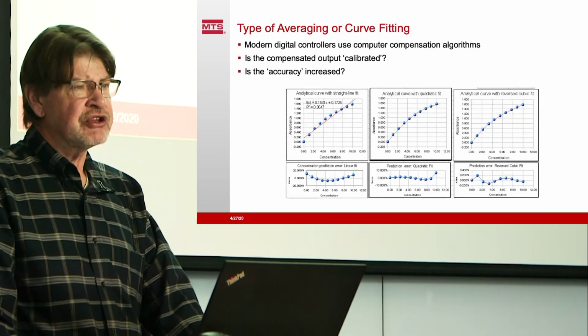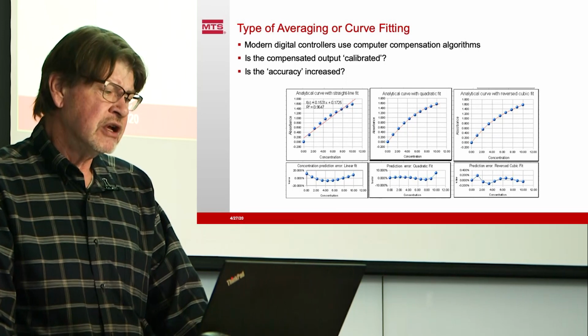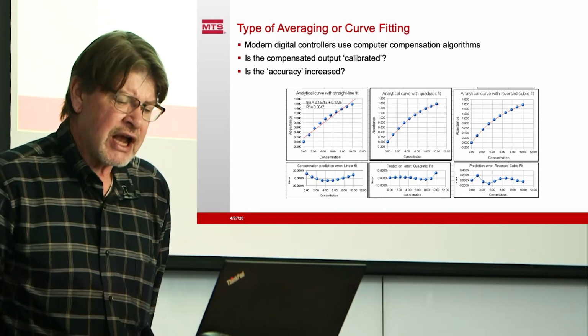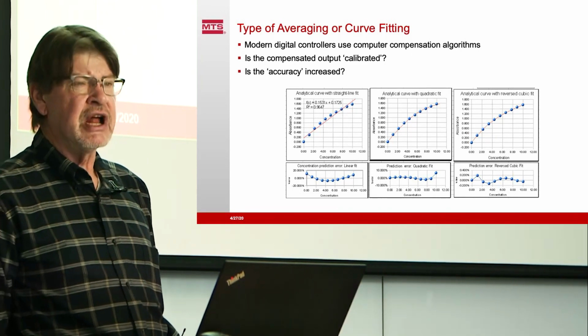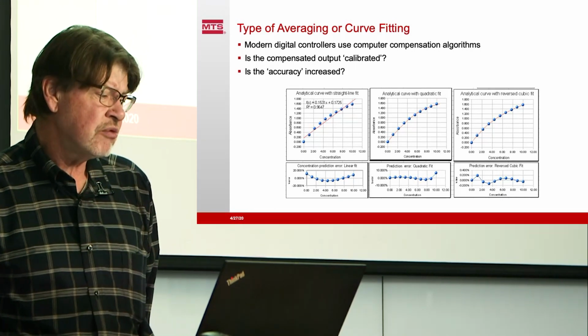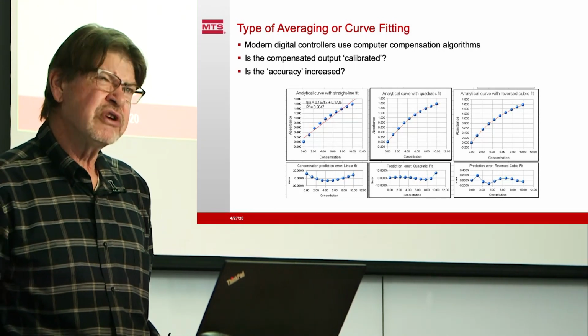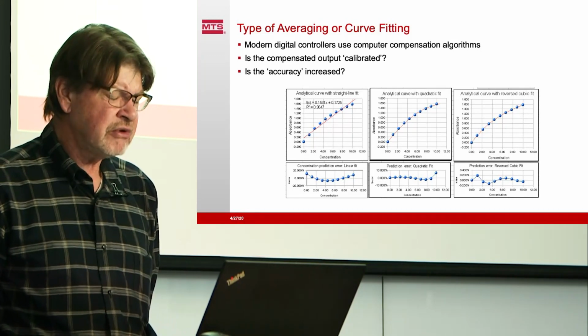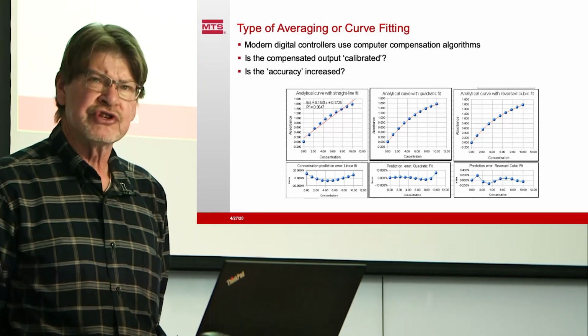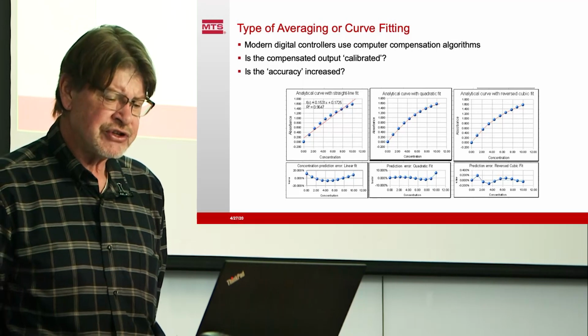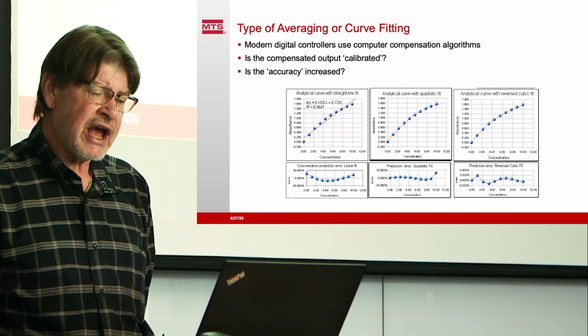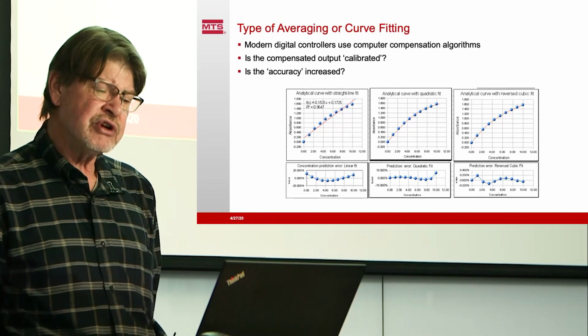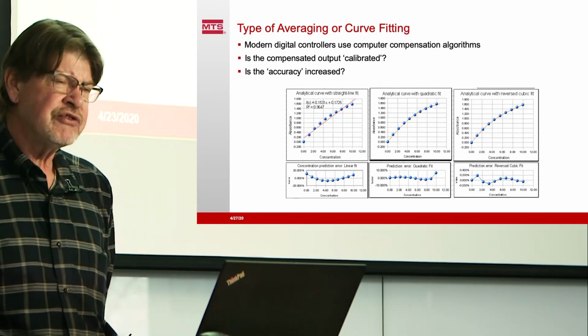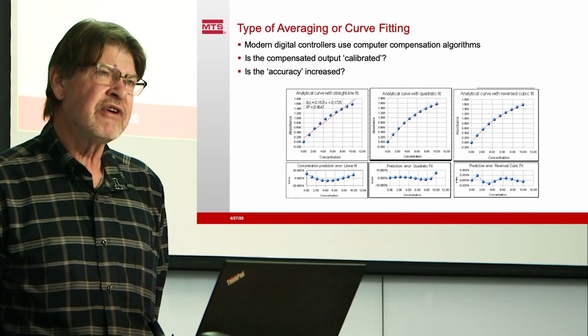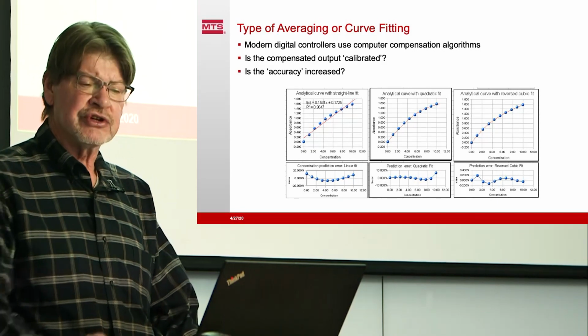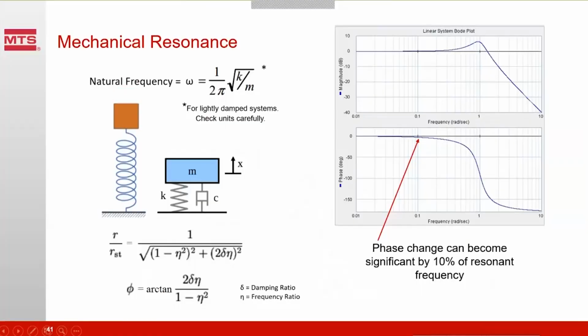Today, especially with computers used in our conditioning equipment, modern digital controllers can compensate for these non-linearities, shall we say, in many different ways. Is the compensated output truly calibrated? I mean, how does that work? I'm not sure our standards quite address all of those issues today with the capabilities to do all this compensation. Is the accuracy of the transducer really increased? Well, the accuracy of the transducer is the same. We're modifying how we read the data and use it to our biggest advantage.